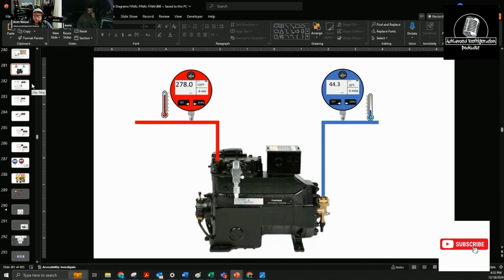Give me some other things, Kev. Bearing wear, blow by, oil pot that's stuck on a high pressure oil system where it's just constantly injecting oil into the side of the compressor. Yeah, and then if the thing empties out, you're just sending discharge gas.